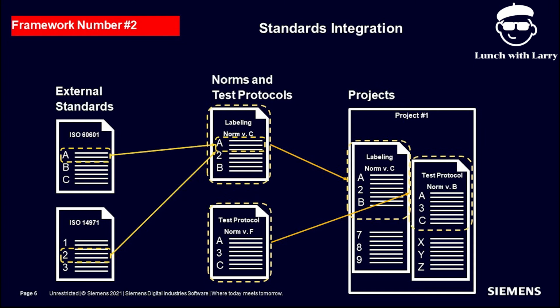So this is really, how do we do reuse? How do we build that into our product set and get 60, 70, 80% of the requirements that we've built in other products built into the new products as well? And of course, not only does this create a lot of leverage from a work standpoint, but it also improves the quality of the development effort, because we're not pulling requirements from scratch, building them new every time we do it. What we're doing is using requirements that were built from products that have been built in the past, and those standards have been improved over time. So we should get to a place where that normative standard library level, those requirements are super solid, have considered everything that's necessary to implement any particular requirement that's associated with the external standards over time. So a very important part of not only reduction of work, but also improving the quality of the work.